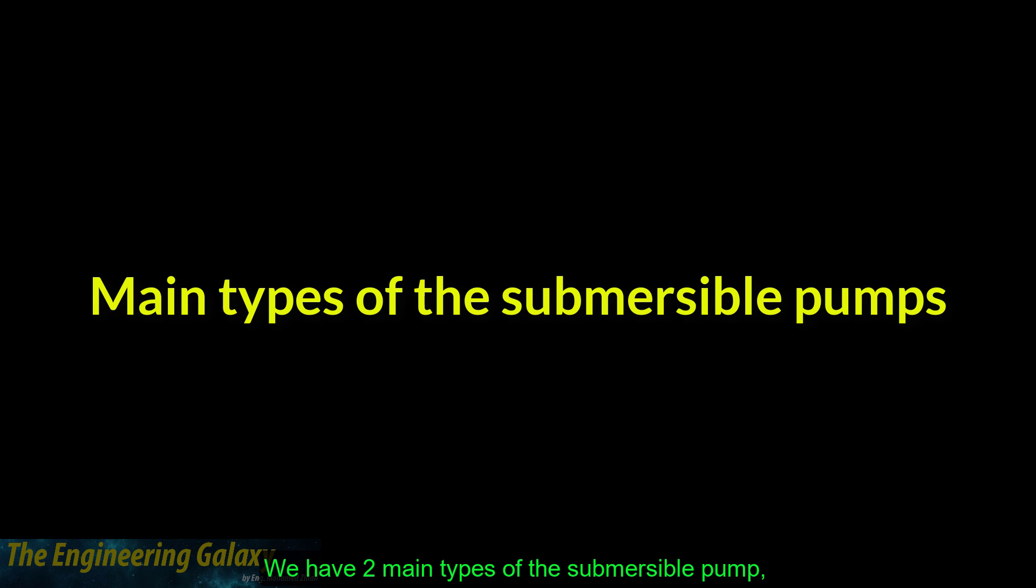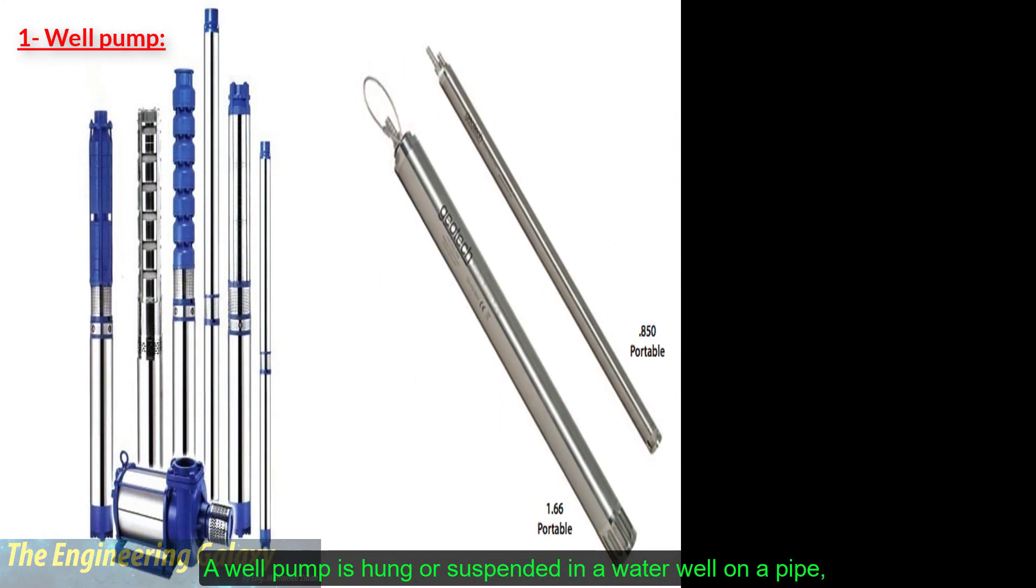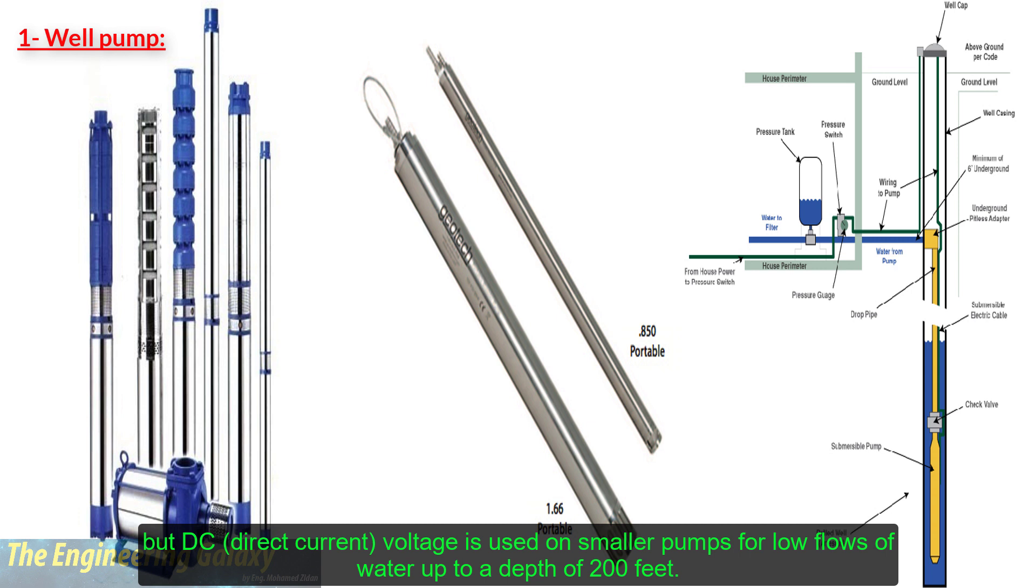We have two main types of submersible pump. The first type is well pump. A well pump is hung or suspended in a water well on a pipe, sometimes to depths past 1000 feet. Well pumps are powered by AC voltage, but DC voltage is used on smaller pumps for low flows of water up to depths of 200 feet.